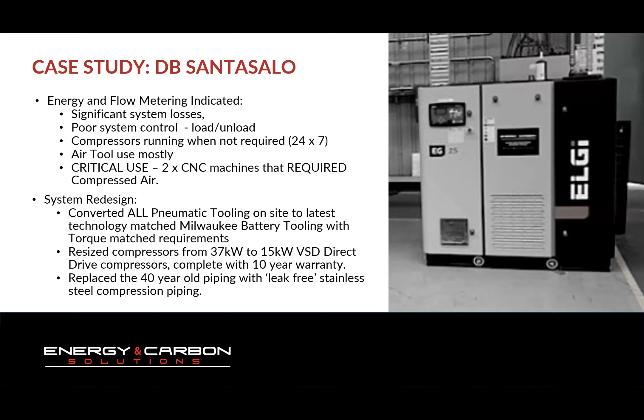Next slide, please. So what we found at the end of the results, and there's the monitoring on the right-hand side, we ended up with an average energy consumption going from 31.7 kilowatts to 7.2 kilowatts on average, which was 77% when we're actually running. And we utilized a lot of the government programs to work with this one. So the total project value was around 124,000, including 2 new compressors, duty standby, dryers, filters, setting up the system, flow meters, power meters, and the 300 meters of piping. We asked and were granted for the audit on this one originally.